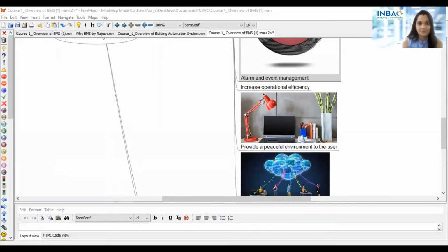Let's take an example. BMS helps equipment run; the schedule is calculated based on run hours. This scheduling prevents equipment from running for longer hours, reducing wear and tear and increasing efficiency, while enabling other equipment with less run hours to operate, ensuring equal runtime for all the machines.